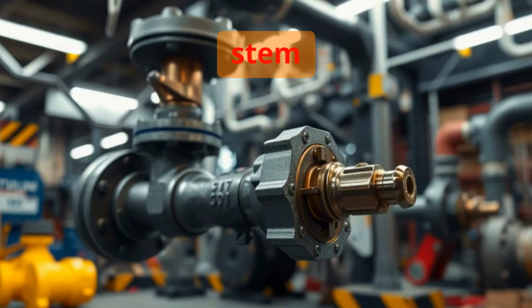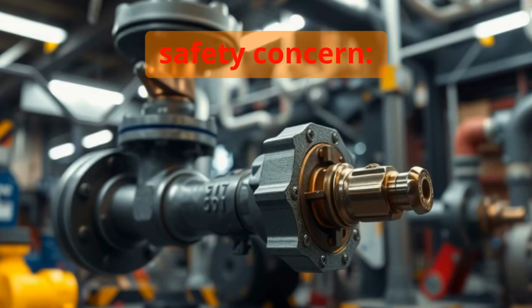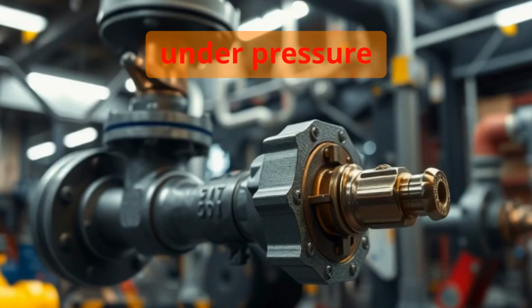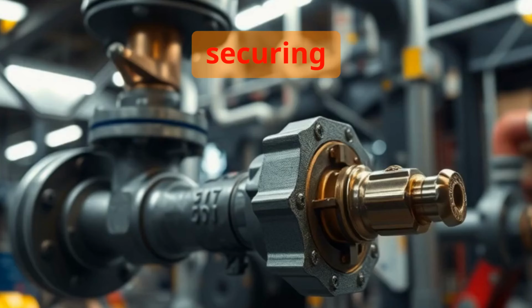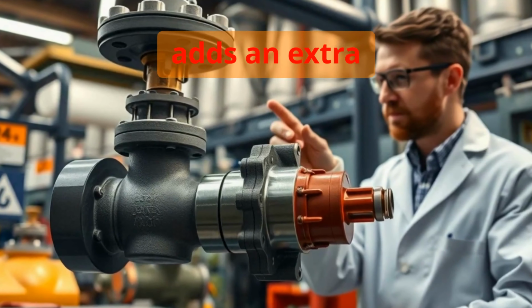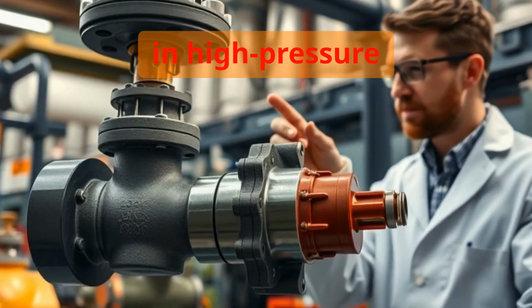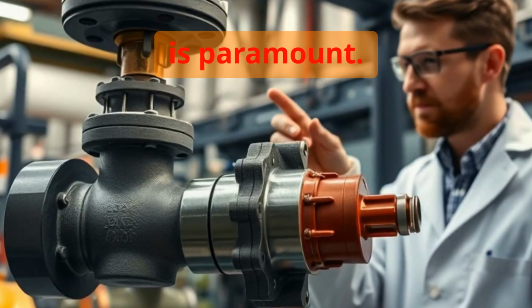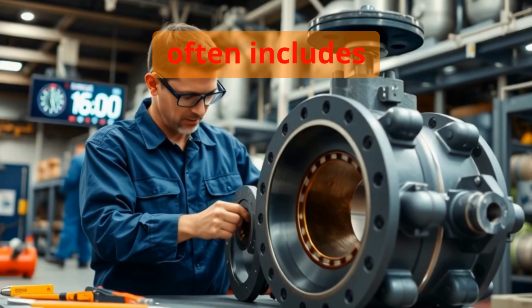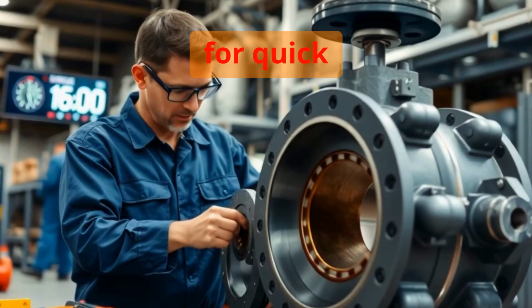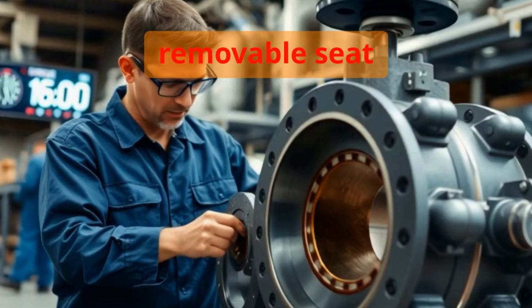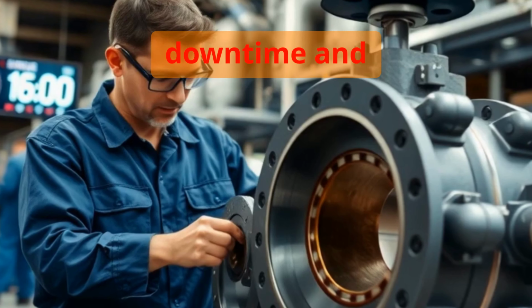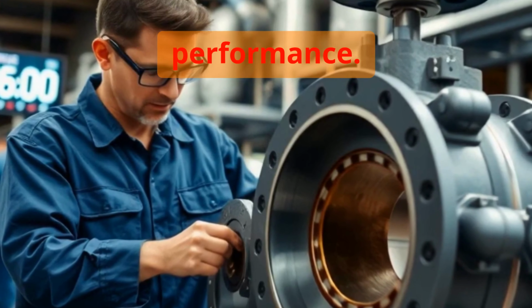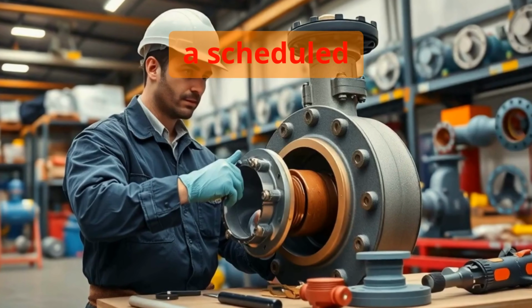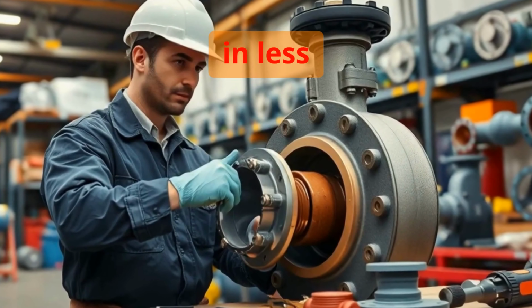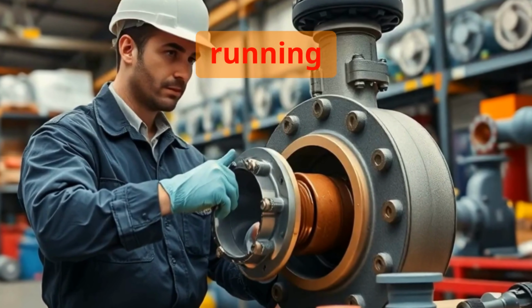The blowout-proof stem design addresses a key safety concern: stem ejection under pressure failure. By mechanically securing the stem, this design adds an extra layer of protection, especially in high-pressure gas services where safety is paramount. Routine maintenance often includes seat ring replacement. By allowing for quick and easy changes of the removable seat surface, this feature reduces downtime and ensures continued valve performance. For example, a scheduled seat ring replacement can be completed in less than 30 minutes, keeping operations running smoothly.